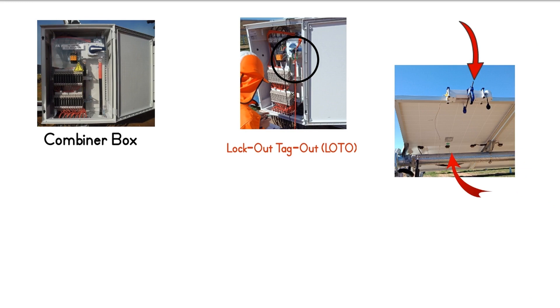Once the combiner box is tested for dead, remove the fuses from each of the positive strings. Using approved type alligator clips, connect the test leads of the IV curve tracer to the positive and negative bus bars.